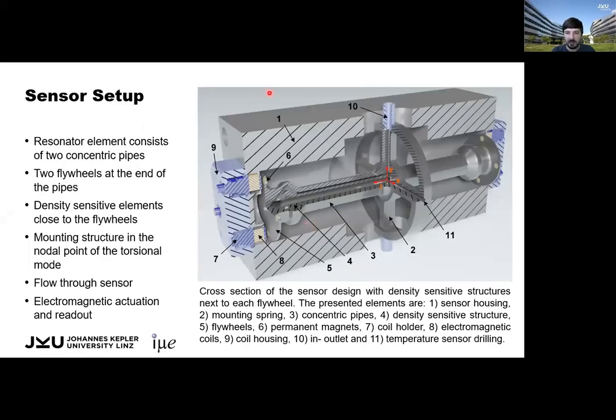Let's have a look at the sensor setup. The sensor consists of a sensor housing and a resonator element. The resonator element consists of two concentrically aligned pipes with flywheels at each end.